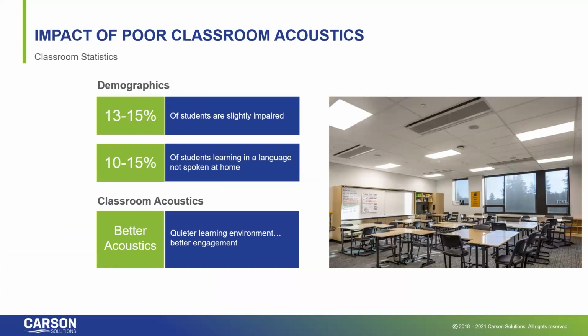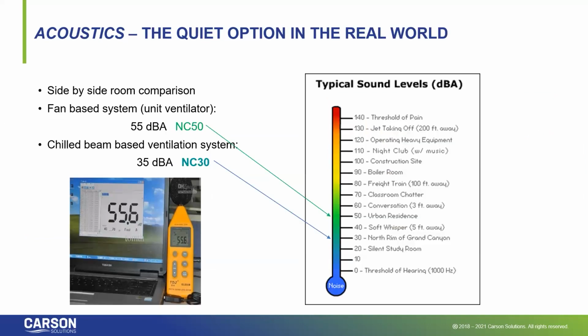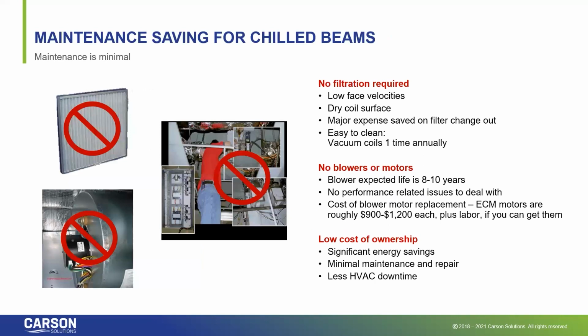Acoustics: if you don't have any moving pieces and parts in the terminal device, there's nothing to make additional acoustical sound. So it's very quiet. It's very accommodative for both learning and working environments. Here's a real world example of a chilled beam based system that delivered 35 dBA for background noise compared to an unfortunate unit vent, which was 55 dBA for background noise. So very big difference in acoustical levels.